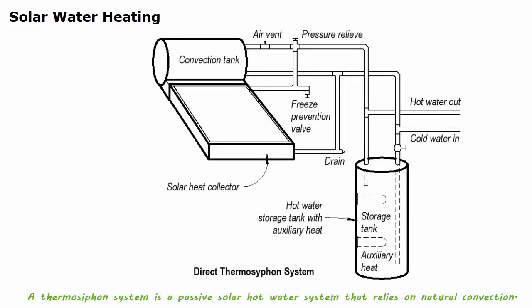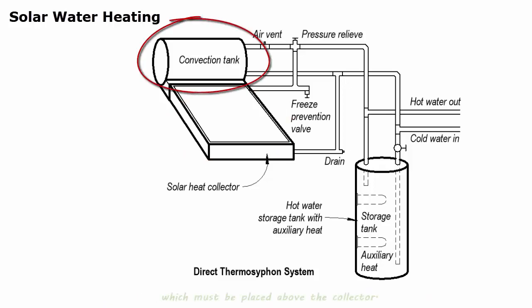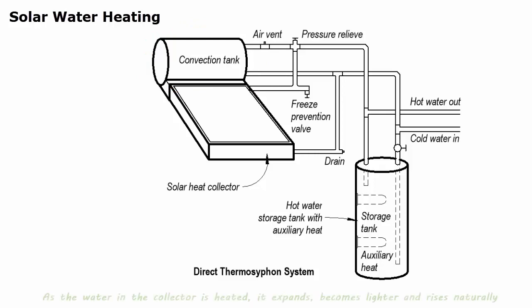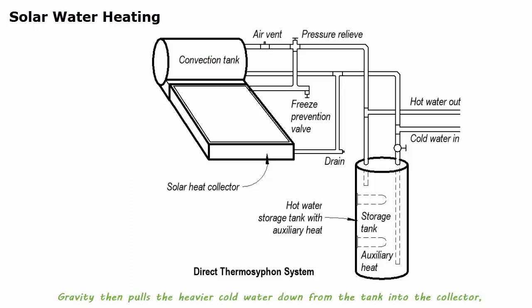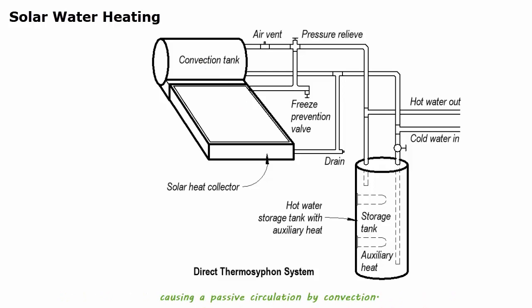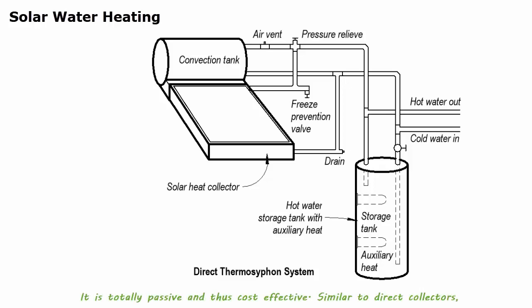A thermal siphon system is a passive solar hot water system that relies on natural convection. Cold water is circulated through the collector into the tank, which must be placed above the collector. As the water in the collector is heated, it expands, becomes lighter, and rises naturally into the tank above. Gravity then pulls the heavier cold water down from the tank into the collector, causing passive circulation by convection. A thermal siphon system requires neither a pump nor a controller—it is totally passive and thus cost effective. Similar to direct collectors, this system is not suitable for very cold climates.